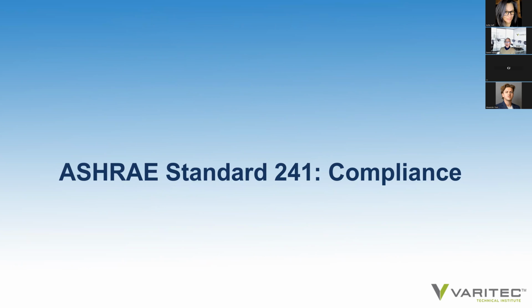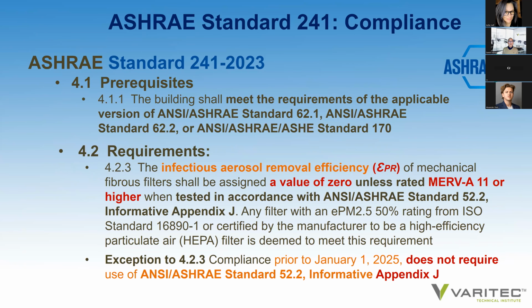So how are HVAC systems to comply with the standard? And I was rather surprised when I discovered this, because I've been presenting on the relevance of MERV filtration on a building system to reduce the risk of infection, as ASHRAE was explicit in its position document on infectious aerosols that a minimum MERV 13 rated filter be used, preferably MERV 14, if the system could withstand the static pressure gain.